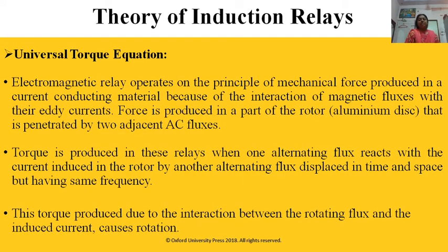This relay works on the principle of induction. That means torque is produced in this relay when one alternating flux reacts with the current induced in the rotor by another alternating flux displaced in time and space but having the same frequency, and due to interaction of rotating flux torque is produced and which causes rotor to rotate or disc to rotate.